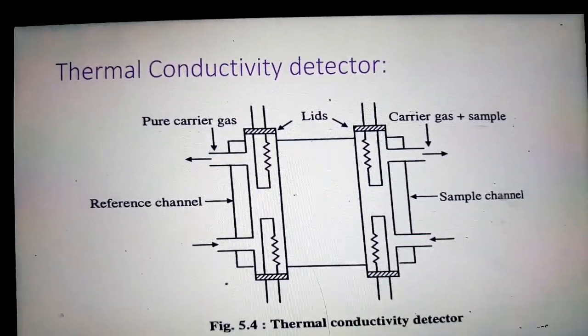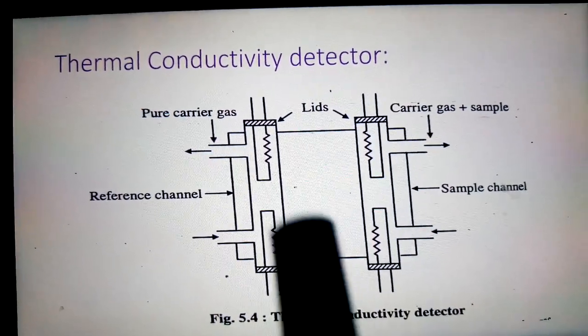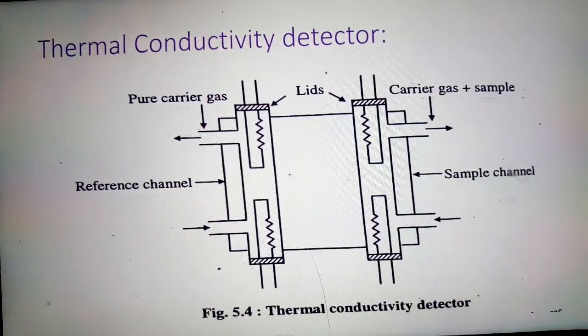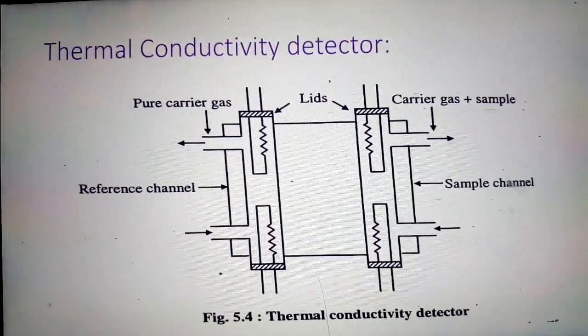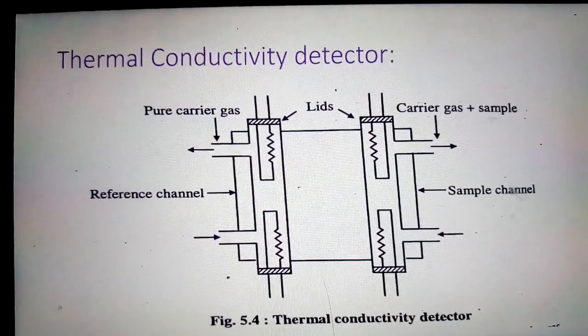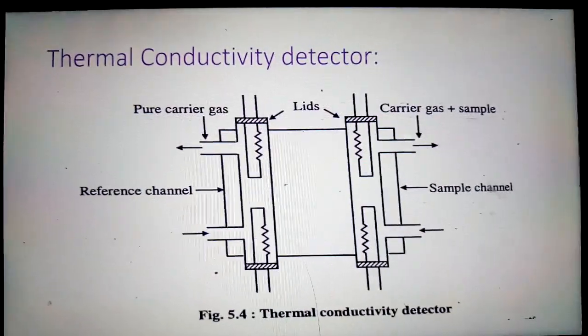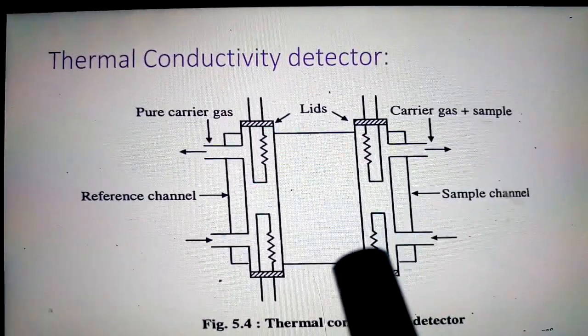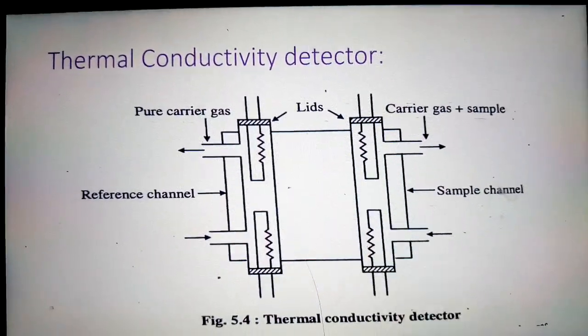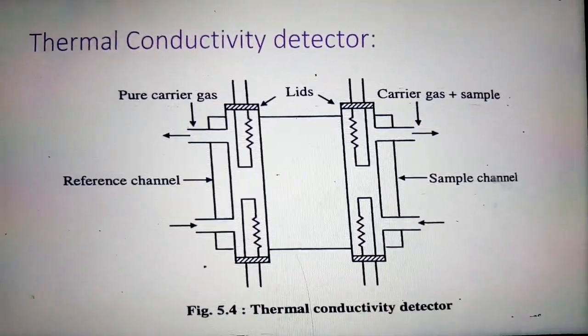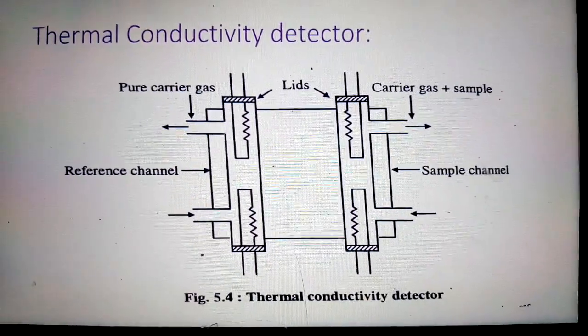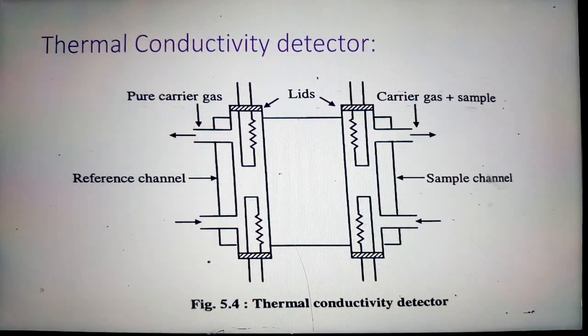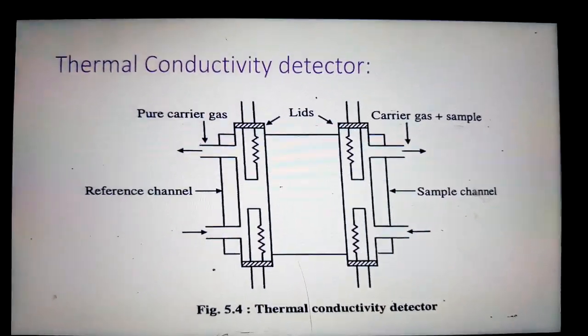These filaments are situated in the Wheatstone bridge circuit. When the pure carrier gas passes over the filaments, the bridge becomes balanced and it gives no signal, meaning the resistance will be the same. When it gives a signal, the signal is fed to the recorder and finally the recorder gives the chromatogram.